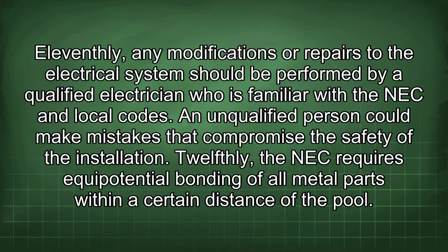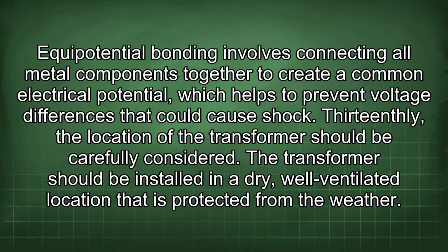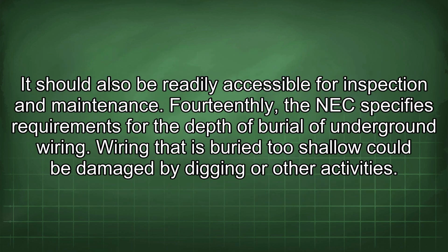12thly, the NEC requires equipotential bonding of all metal parts within a certain distance of the pool. Equipotential bonding involves connecting all metal components together to create a common electrical potential, which helps to prevent voltage differences that could cause shock. 13thly, the location of the transformer should be carefully considered. The transformer should be installed in a dry, well-ventilated location that is protected from the weather. It should also be readily accessible for inspection and maintenance.